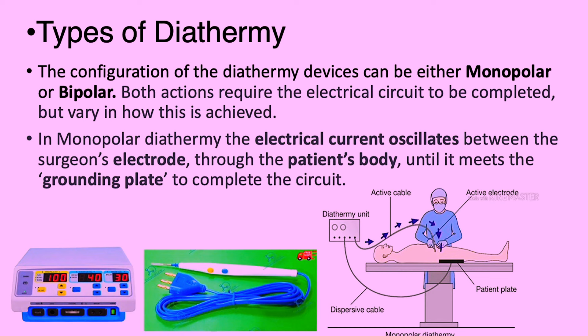The types of diathermy: the configuration of diathermy devices can either be monopolar or bipolar. Both require an electrical circuit to be completed but vary in how this is achieved. In monopolar diathermy, the electrical current oscillates between the surgeon's electrode through the patient's body until it meets the ground plate to complete the circuit. This is the ESU — the electrosurgical generator.